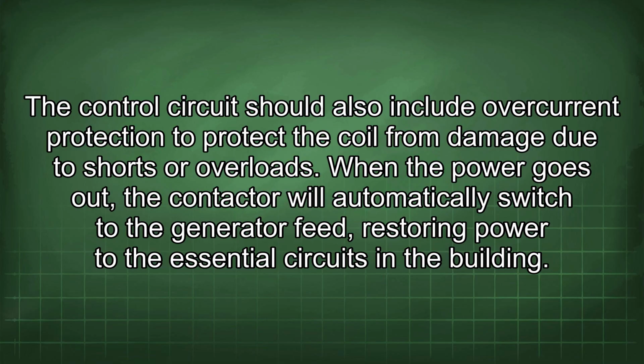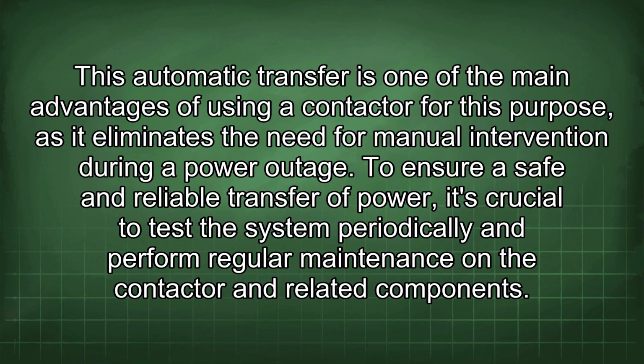When the power goes out, the contactor will automatically switch to the generator feed, restoring power to the essential circuits in the building. This automatic transfer is one of the main advantages of using a contactor for this purpose, as it eliminates the need for manual intervention during a power outage. To ensure safe and reliable transfer of power, it's crucial to test the system periodically and perform regular maintenance on the contactor and related components.